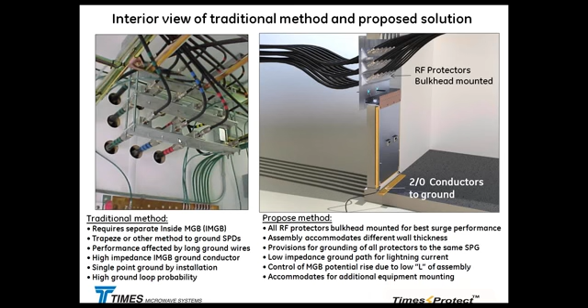If you came to me and said, Bogi, I need a 25-volt protector—if I put this protector here, you see the traces, 25 volts on the positive side, you get that 25 volts. But if I put the same protector here and add 1.5 to 2 feet of wire, that 25-volt protector becomes more like a 700-volt peak-to-peak protector. That's the best hidden secret of the industry. Let's not even talk about lead length.